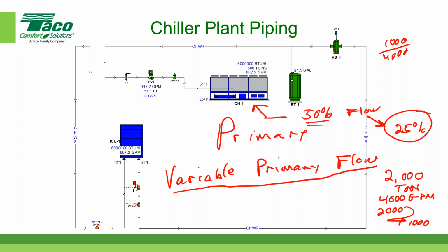And so now you can see one of the advantages in order to optimize a chiller plant is to consider using multiple chillers because you can get the flow capacity quite low. And again, just for simplified, oversimplified examples, if I made 4 chillers at 25%, then instead of the minimum flow for the entire system going to 25%, it would go to 12.5, which would be half as much. So that's the major difference between a variable primary flow and primary secondary systems. One of the advantages, you only need to have one set of pumps. Now, again, if we had multiple chillers, there's one there, there's one there.